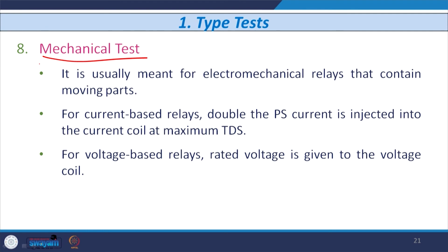The last type of type test is known as the mechanical test. This mechanical test, as I told you earlier, is performed only in the case of electromechanical relays, because they usually contain moving parts. The next generation relays, like static relays, digital relays, adaptive relays and other relays, do not contain moving parts, so this type of test is not performed on them.